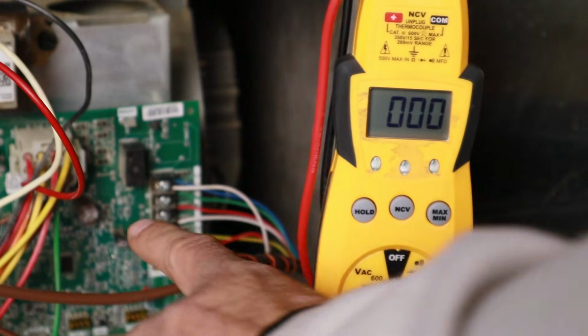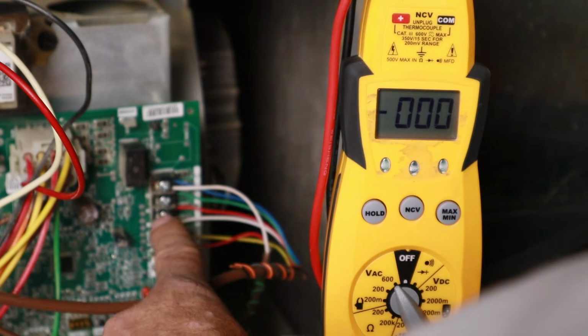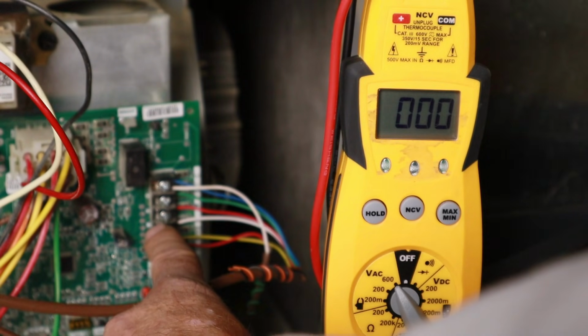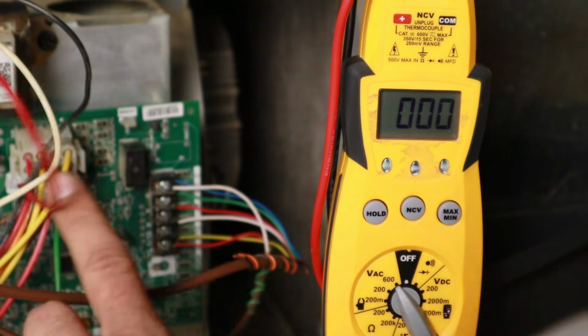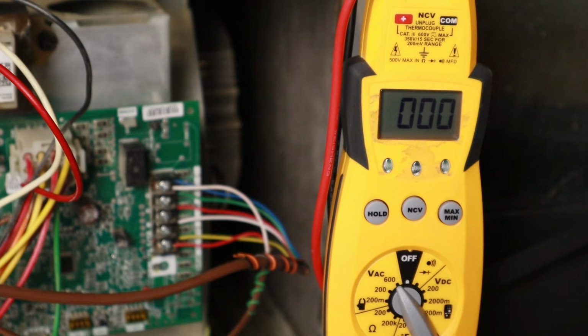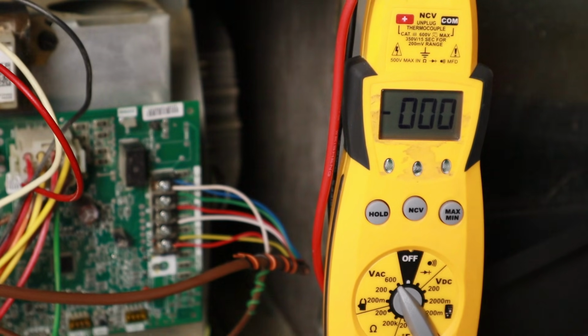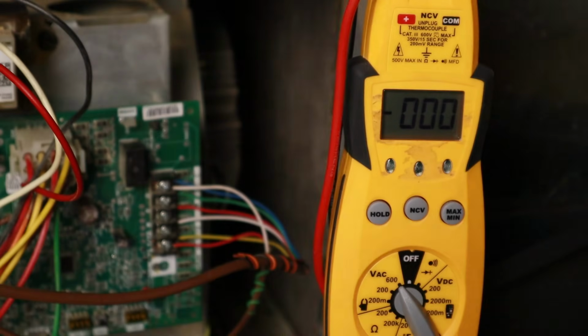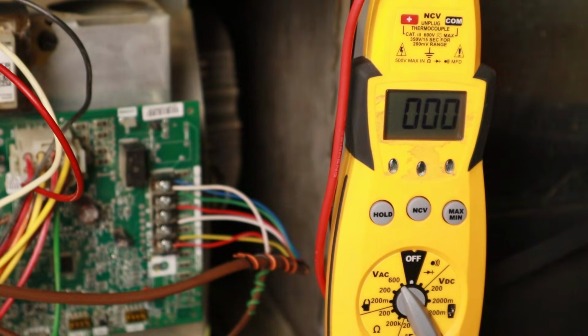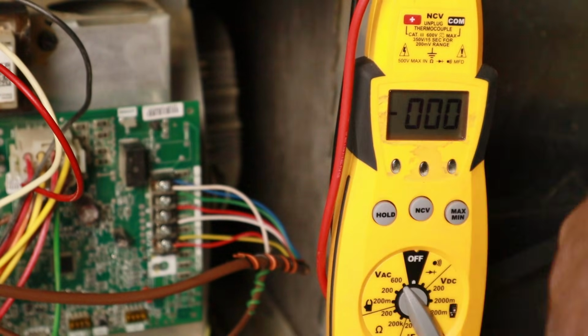All right, so now I have 24 volts on my R terminal here on my control board. That 24 volts is going up to the R terminal on my thermostat. Now I turn the thermostat into heating mode. I'm going to turn the power back on the unit, and what's going to happen is the 24 volts is going to go up to the thermostat.